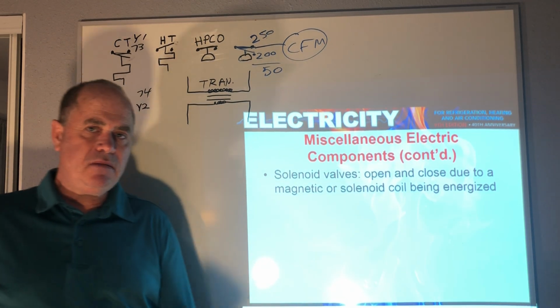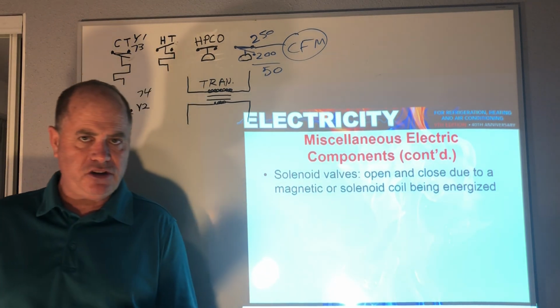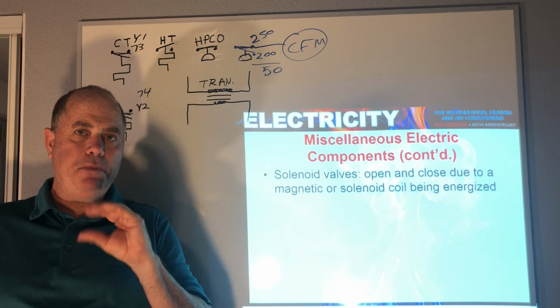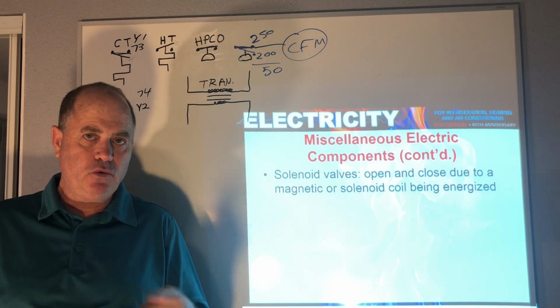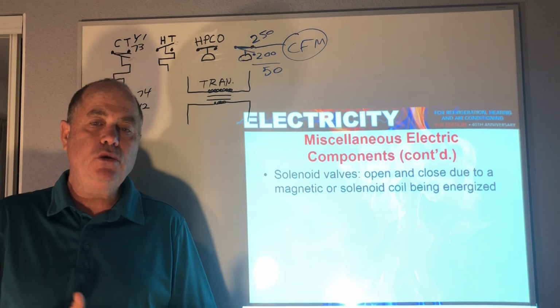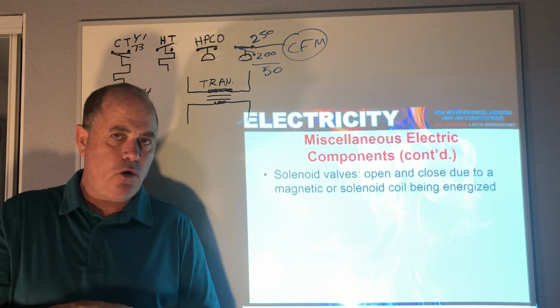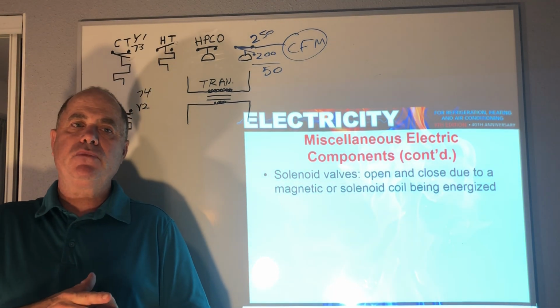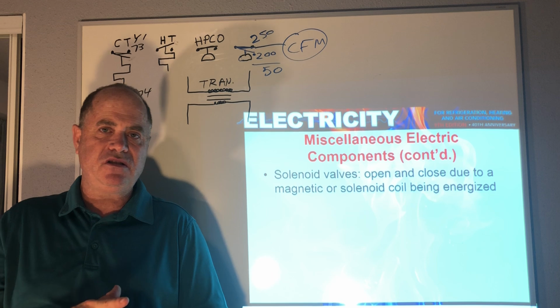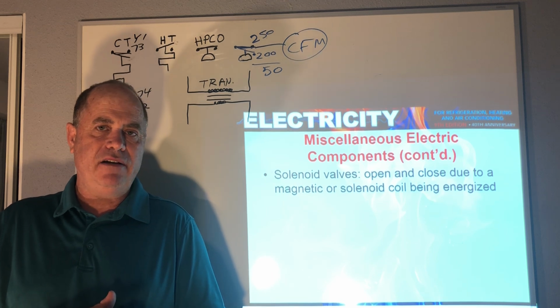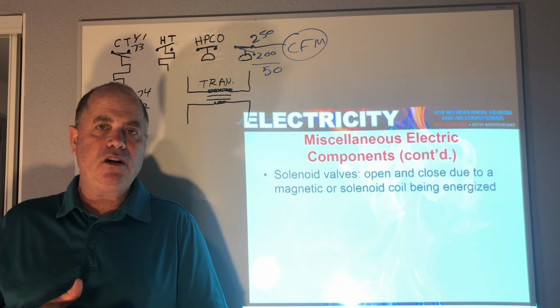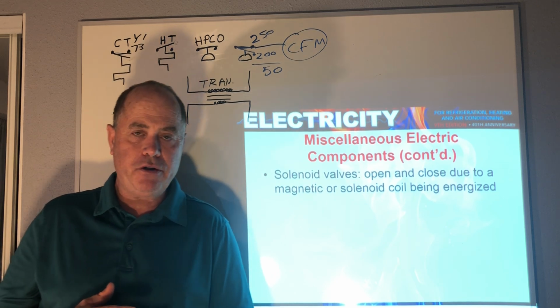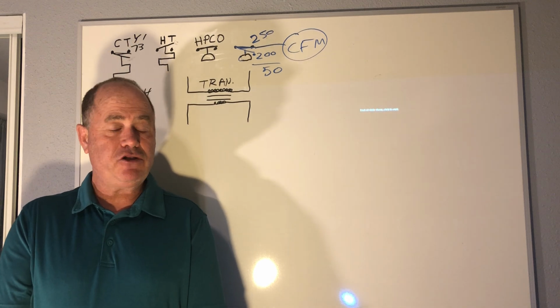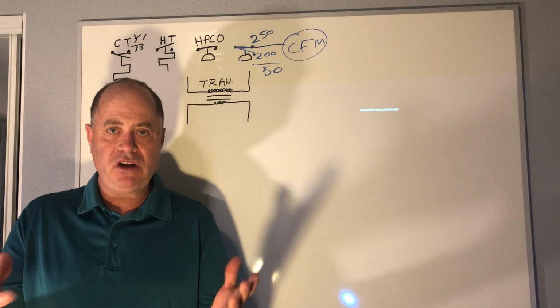Solenoid valves. Sometimes we use hot water or chilled water on large systems, and we have solenoid valves that open or close to let the hot or chilled water flow in order to provide heating or cooling. Also on refrigeration only, we sometimes have pump down systems where liquid line solenoid valves are energized, and quite often these are controlled with thermostats. And that concludes my lecture on pressure controls, thermostats, transformers, and other electrical components.